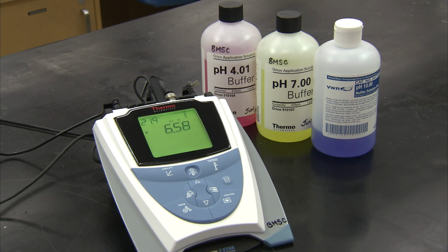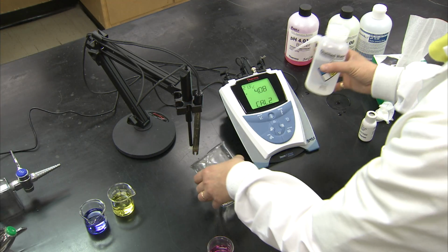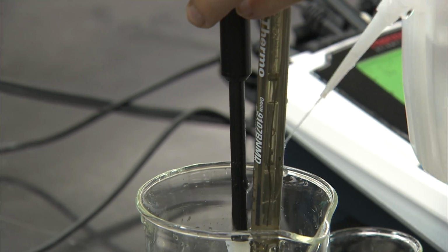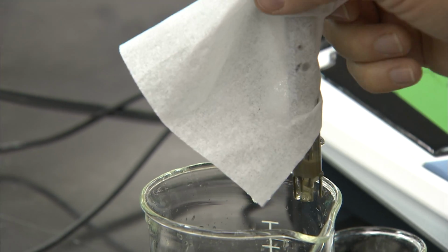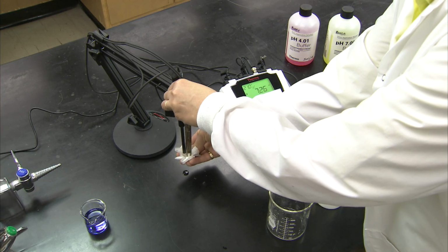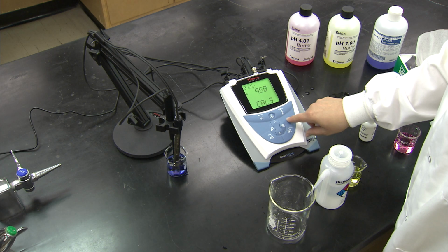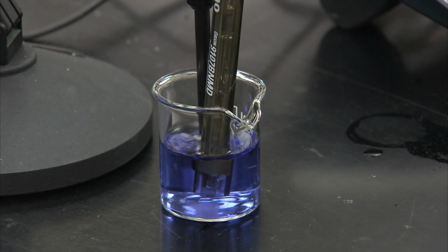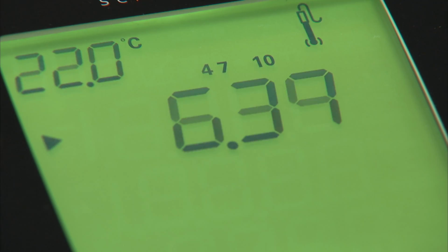Now that the pH meter is calibrated, it can be used in much the same way to measure a sample. The probe is rinsed and blotted. It is immersed in the sample. The stirrer is turned on, and after the reading stabilizes, it can be recorded. You will see that the pH meter has a consistent reading when the screen stops flashing the pH icon.